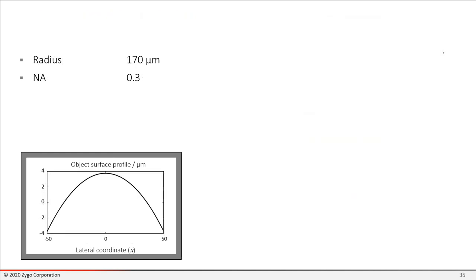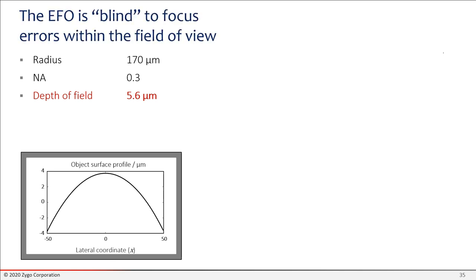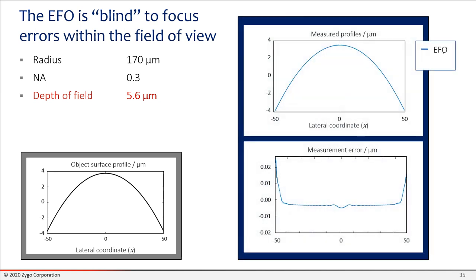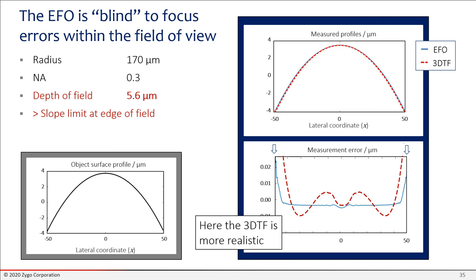Let's try something a little bit more challenging. Here we have a part with a lot of surface departure, plus or minus 4 microns, which compared to the depth of field is pretty large. And we're going to expect to see some difficulties here because the model, the EFO model is blind to focus errors within the field of view. The previous example, we were putting the object at different focus positions overall, defocusing the instrument. But this is a case where the departure itself is introducing defocus. If you go ahead and run the EFO model, you see pretty good results. Measurement error is close to zero, except at the very edges where the light is actually falling outside the acceptance cone of the numerical aperture. But if you run the 3D model, the 3D transfer function model, you see variations on the order of 10 nanometers almost. These are caused by focus effects. And we expect that in this case, the 3DTF approach is going to be more realistic than the EFO.